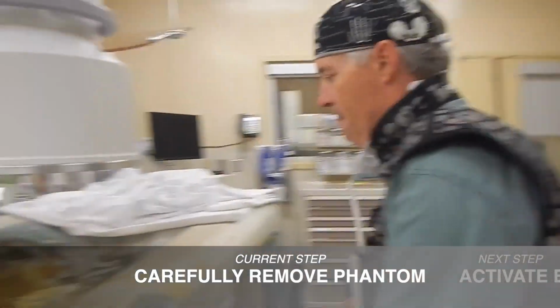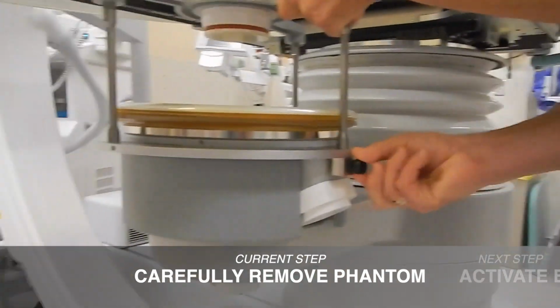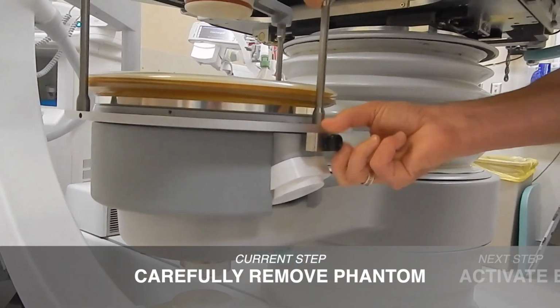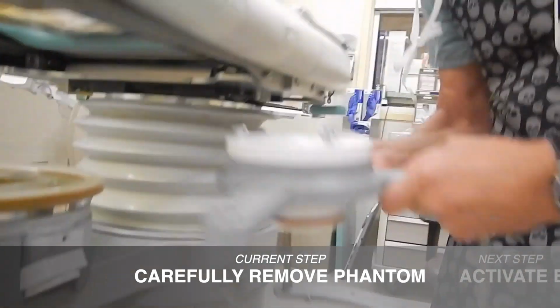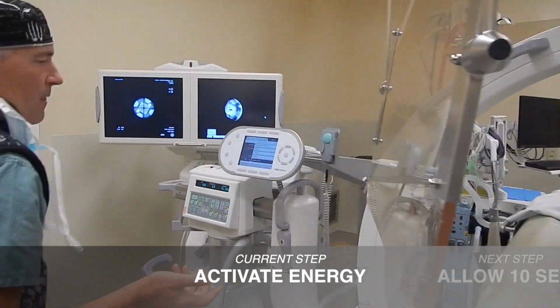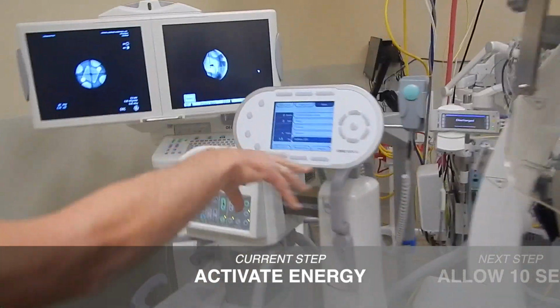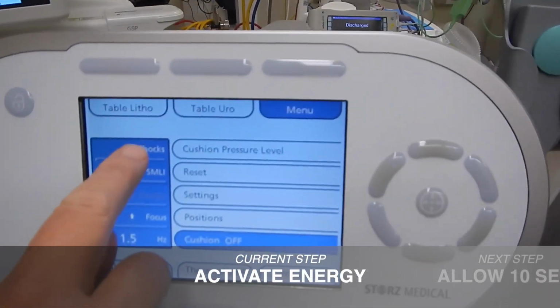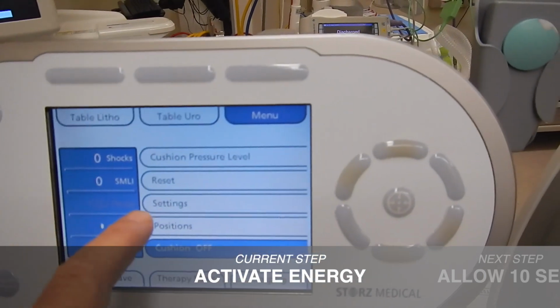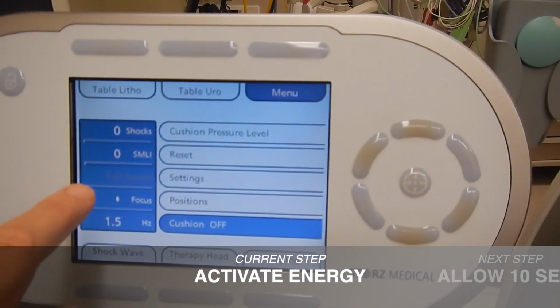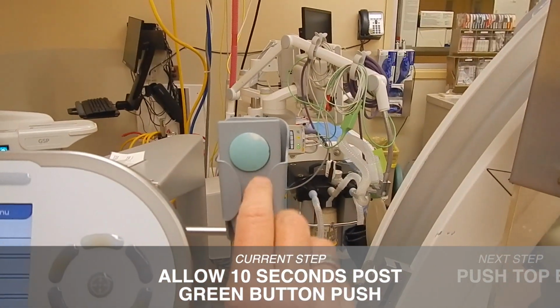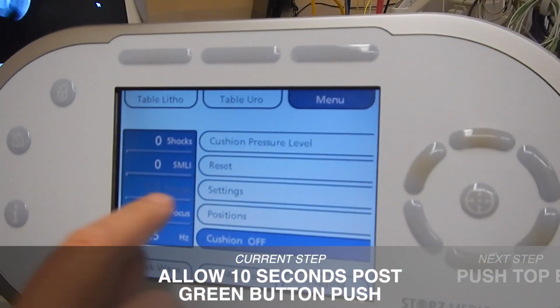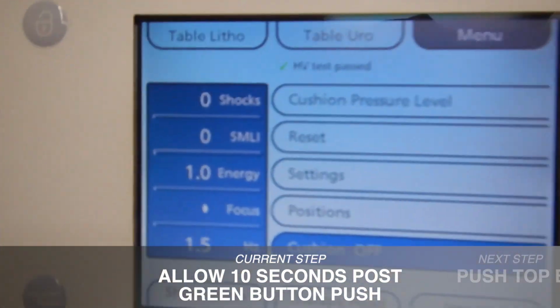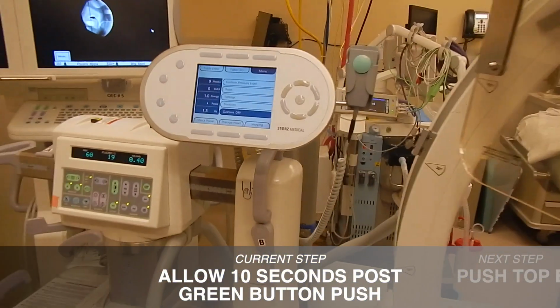So now what you can do is take the phantom off. It's a little bit heavy, so just be careful once you unscrew it, but you have a good grip on it. Slide it back. So we're going to assume that we have a patient on the way. This panel is showing us that everything is ready to go. It's highlighted in white except the energy. So what the machine wants is a high voltage test. All you do for that is lift this slightly, press this green button, the trigger button, let go, and then in about 10 seconds this will turn white. It's just a simple test that will allow you to have energy when the time comes.